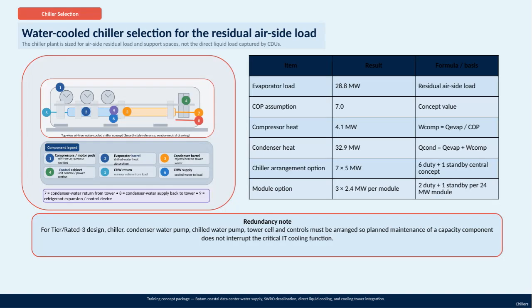Let's talk about chiller selection for the residual airside load in our data center cooling system. We're focusing on water-cooled chillers designed specifically to handle the airside residual load and support spaces, rather than the direct liquid load managed by the CDU units. Based on the data, the evaporator load is 28.8 megawatts, which reflects the residual airside cooling demand. We assume a coefficient of performance, or COP, of 7.0 as a conceptual value. This means for every unit of power we put into the compressor, we get 7 units of cooling output. Using this, the compressor heat input is calculated at 4.1 megawatts, while the total condenser heat, comprising both evaporator and compressor heat, is about 32.9 megawatts.